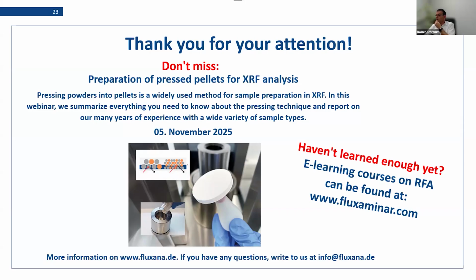So let me see, any more questions here? Not for the moment. You know that you can always send me an email if there's any open question and you would like to discuss perhaps also some software issues, how you can really perform this. And also what happens sometimes is when you break a drift correction glass, that it falls down, it drops down, then it's a special procedure how you will introduce a new version into your software. And there also we can help you.